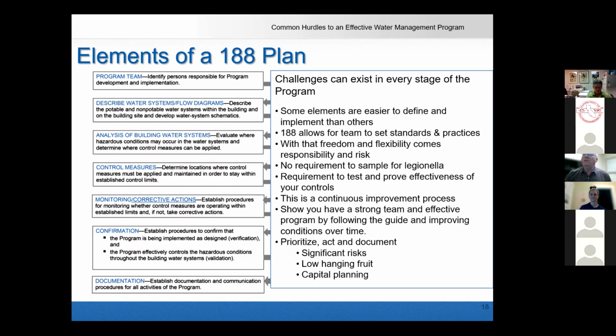There are, in general, three conditions that exist when we collect samples. We didn't find any, so we're feeling pretty good. We found a whole bunch, so we know we've got to do something. It's the one in the middle that causes the problem - we got some hits but not all hits, some colony forming units close to that 10 range. What do we do about that? Those are the conversations your team needs to have before you get the data.